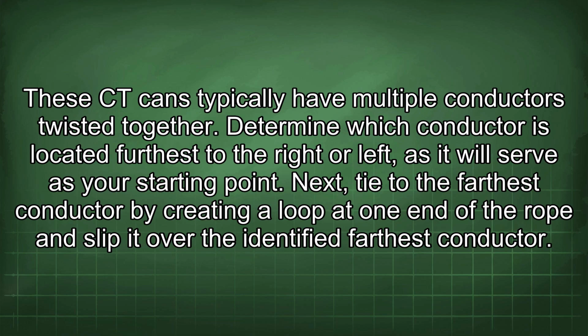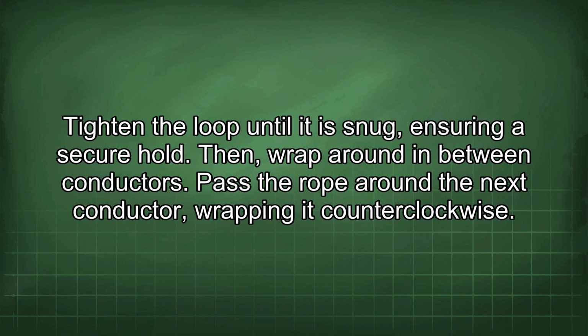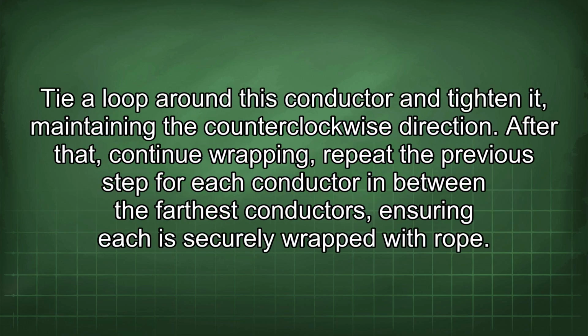Next, tie to the farthest conductor by creating a loop at one end of the rope and slip it over the identified farthest conductor. Tighten the loop until it is snug, ensuring a secure hold. Then wrap around in between conductors. Pass the rope around the next conductor, wrapping it counterclockwise. Tie a loop around this conductor and tighten it, maintaining the counterclockwise direction.